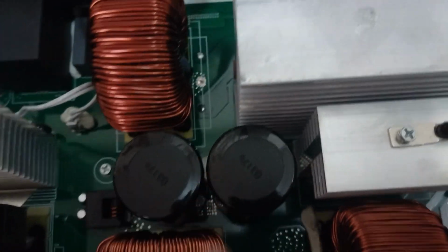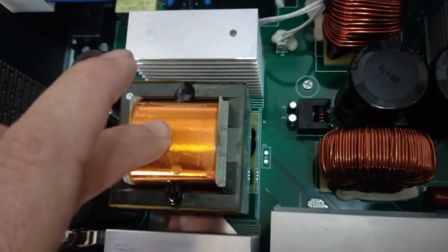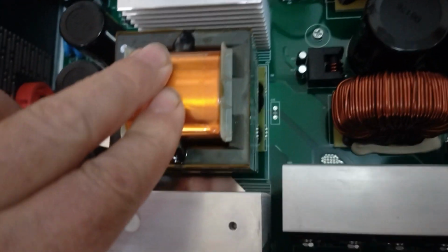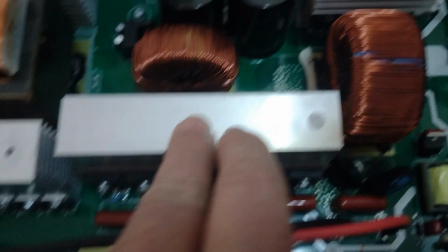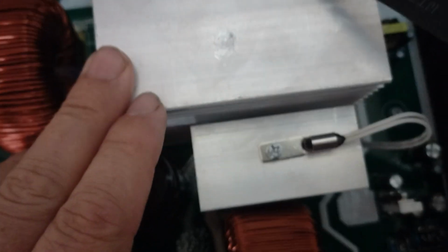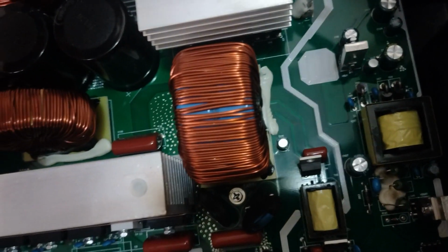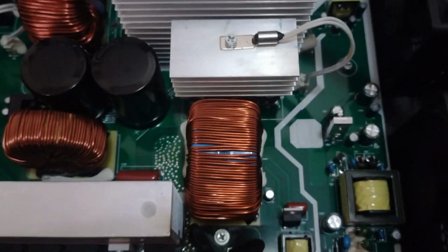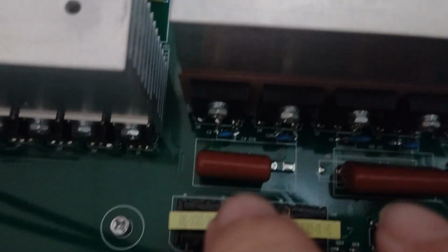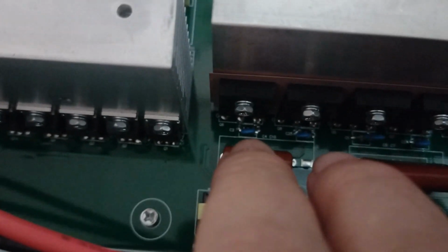So on this bus, it could be the output rectifier from the 48 volt to 380 volt transformer. It could be the AC output H-bridge, or it could be the MPPT converter. So I guess what we'll start doing first is we will check all of these IGBTs. When they go bad, they typically, but not always, will fail gate to source, or gate to emitter, I guess, on an IGBT. So we'll check all those, check all these, and then we'll check the low side. So this is 48 volt to 380 volt sort of power stage. So we'll check those.